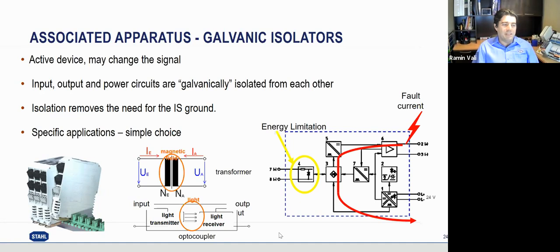The isolation basically has some other benefits, like the resistor is not there anymore. Basically, the internal resistance of an isolator is very low, so we don't need to worry about the voltage drop across it. And because it has some more electronics inside, it can also change the signal. So we can have a temperature input connected to the isolator, and then we get a 4 to 20 milliamp signal as an output, or change 4 to 20 milliamps to a voltage signal. So that's a more flexible system because we have more electronics inside it.